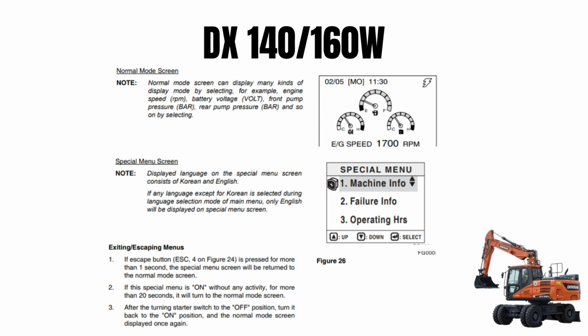Entering, accessing and exiting, escaping menus. Entering the menus: when the normal mode screen is displayed, if the enter button and escape button are pressed simultaneously for more than 3 seconds, the normal mode screen will change to the special menu screen. So how can you access it? You press the enter and escape buttons simultaneously for more than 3 seconds.